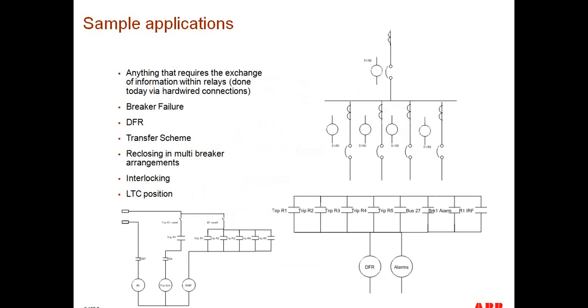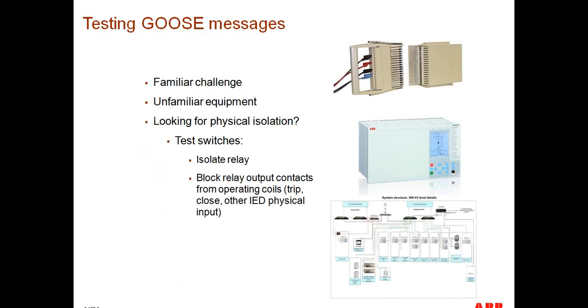Now, some sample applications. We've mentioned that throughout the presentation, but essentially anything that requires the exchange of information from one relay onto the other, which today is done via hardwired connection. So breaker fail could be one candidate, digital fault recorder signals to initiate a DFR, another candidate, transfer schemes, which again require a significant amount of hard wiring from one device onto another, could be a candidate to apply GOOSE messages. Reclosing in multi-breaker arrangements where the reclosing function is outside the line protection relay. Interlocking and devices to monitor the position of the load tap changer, and again, just about anything that you can think of where information is being shared from one device onto another.